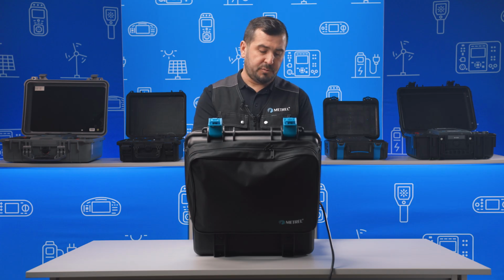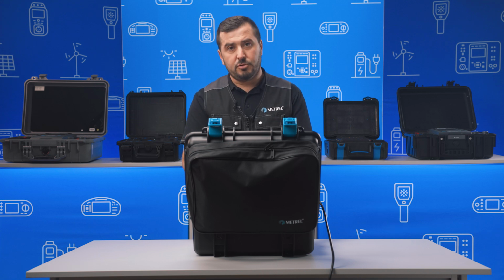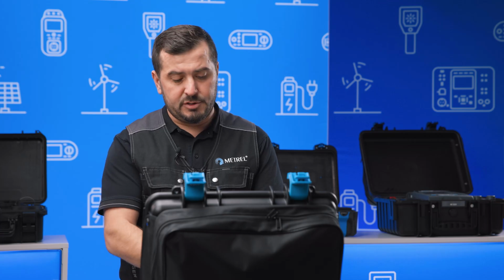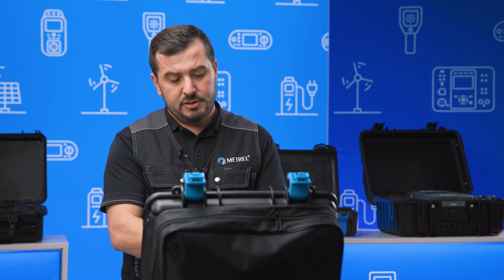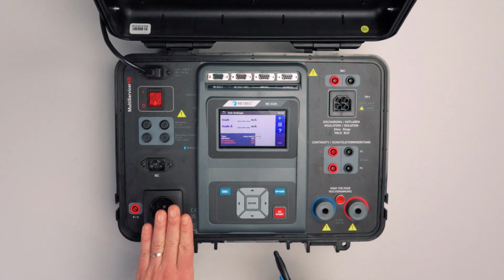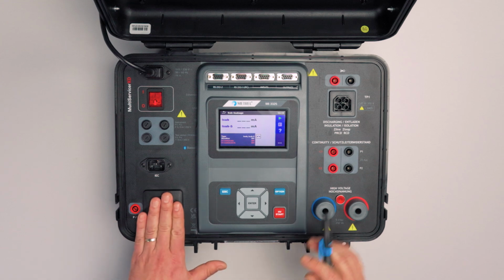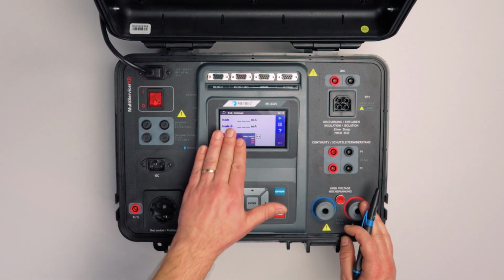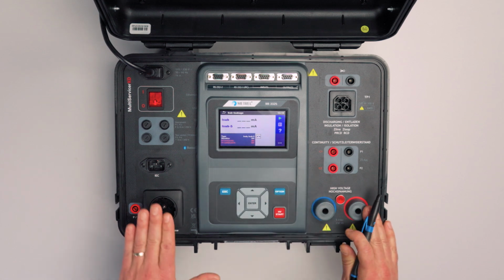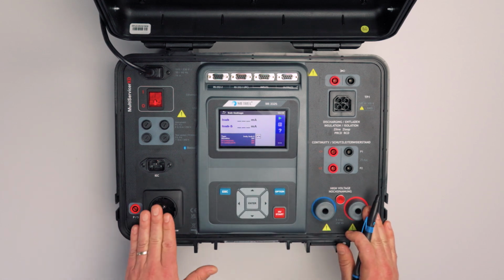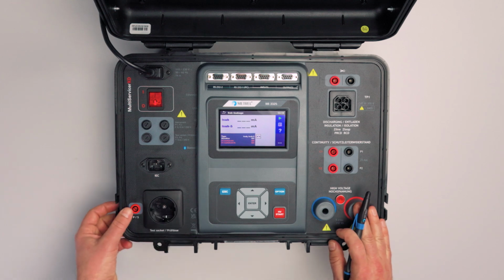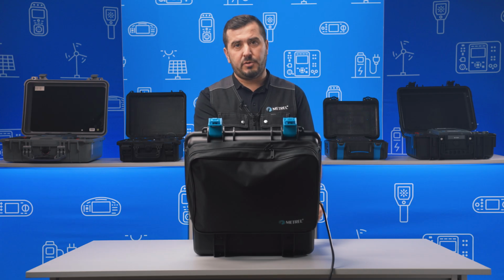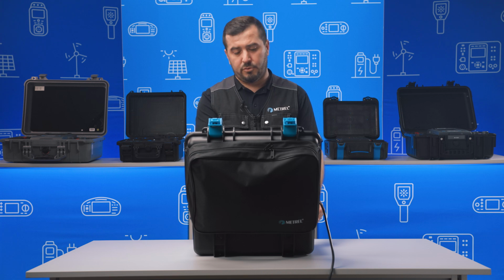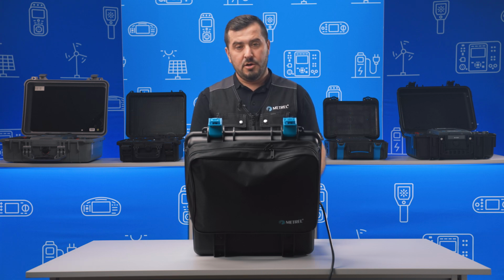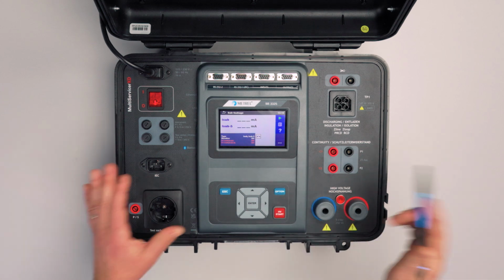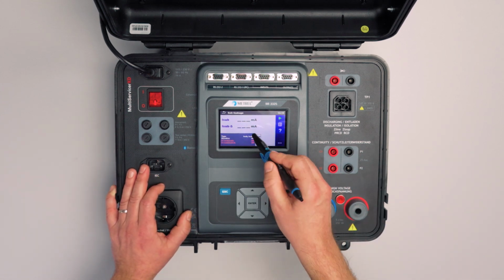If we focus on each specific measurement, the substitute leakage measurement has the same logic as the previously shown insulation resistance. So we can perform the test from the socket between phase and neutral conductor against PE, or the test with the probe. Here, connect the device, and the test will be performed between live and neutral against the probe. So for class 1, class 2 equipment testing, or for the combined equipment testing, or you can always decide to perform these measurements independently.